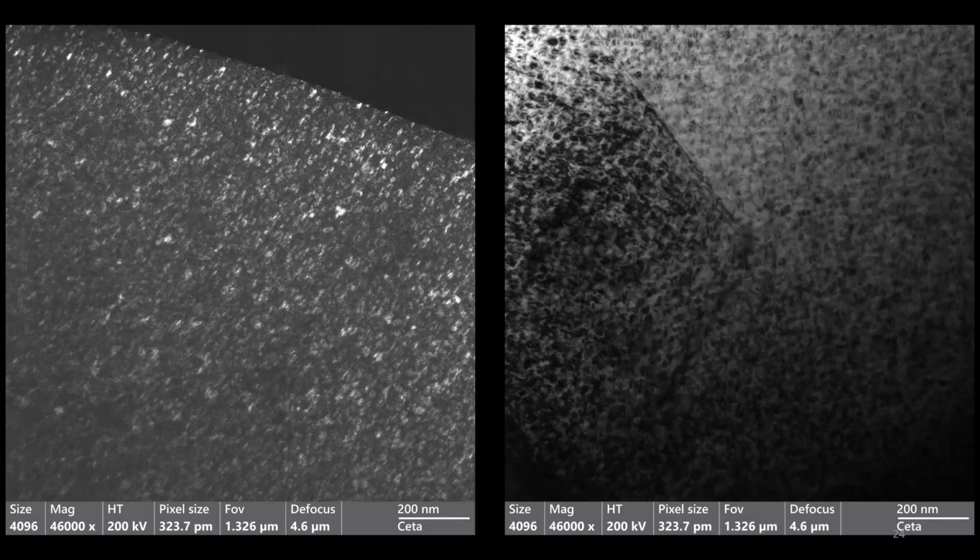This is dark field imaging. So we talked about diffraction. You have your primary beam, you have your diffracted stuff. If you just get rid of the primary beam, you can get dark field. And that's what you do in an optical microscope. But in a transmission electron microscope, you can take it one step further. You can pick which one of those diffracted spots. Say you have, even in a polycrystalline, you can pick which ring you want to put your aperture around. And you can get rid of everything but that.